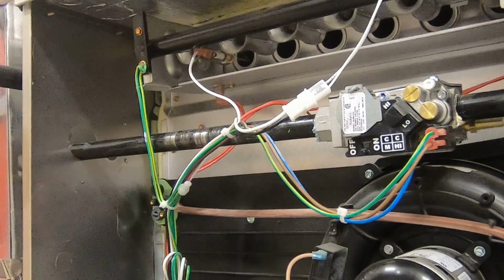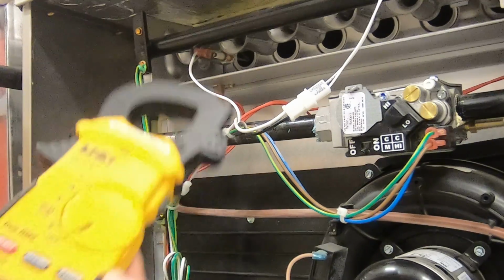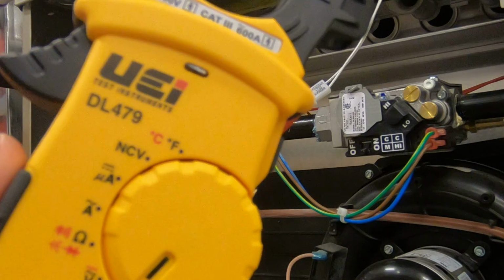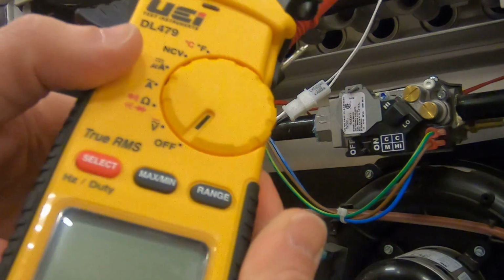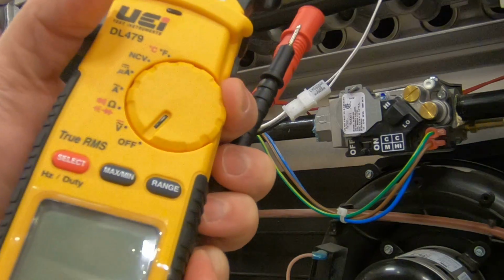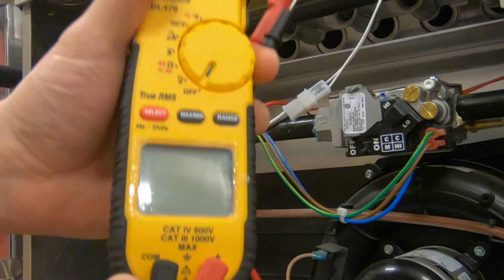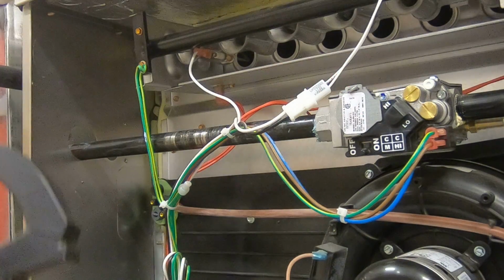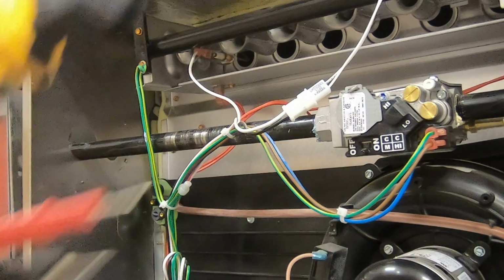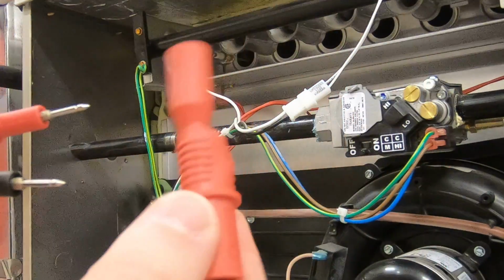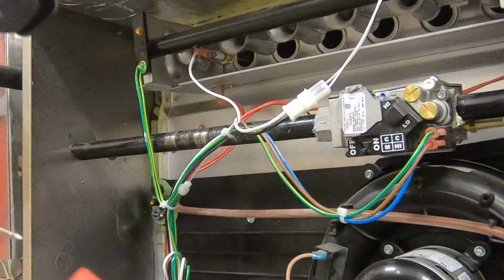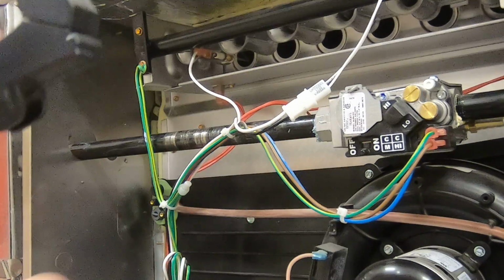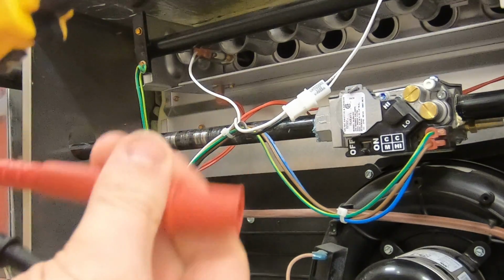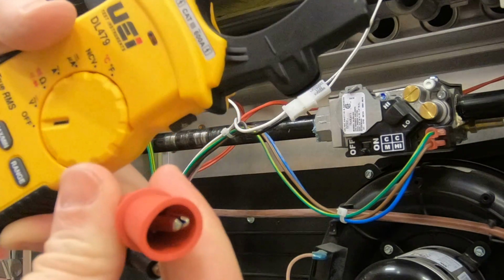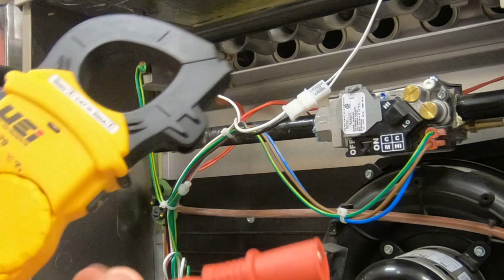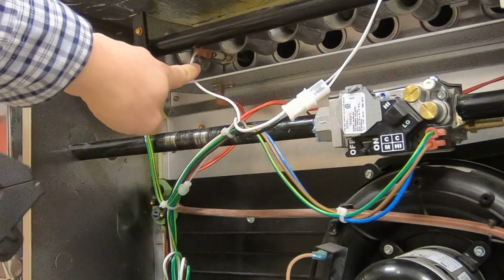This video is going to show you how to check a flame sensor signal with the DL479 clamp-on multimeter. So first thing to do is make sure your leads are hooked in, and you're going to want to make sure that the end of your leads is your alligator clip. So it's going to screw on like this, and then the end you can depress and see it open.